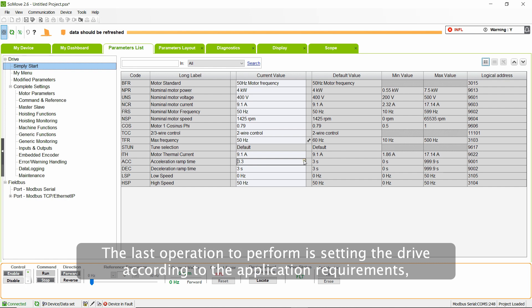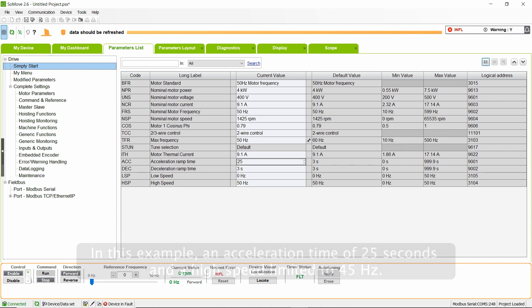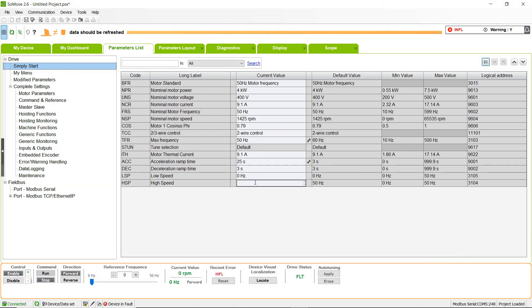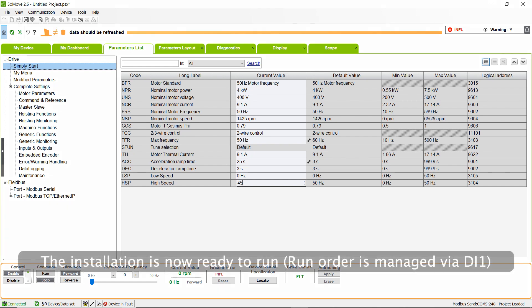The last operation to perform is setting the drive according to the application requirements. In this example, an acceleration time of 25 seconds and a high speed limited to 45 hertz. The installation is now ready to run.